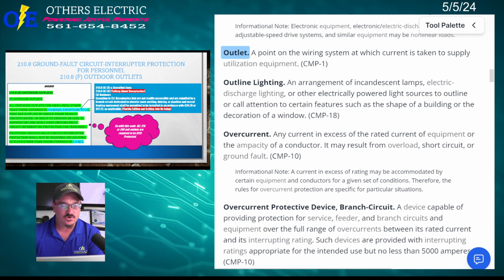Okay, all outdoor outlets for dwellings other than those covered in 210.8(A)(3), exception to 3, that are supplied by single-phase branch circuits rated 150 volts to ground or less, 50 amps or less, shall have ground fault circuit interrupter protection for personnel. So anything 50 amps or less, 120, 240 doesn't matter, because if you got a 240 volt outlet for a condensing unit, it doesn't matter. When you go either phase to ground, it's 150 volts or less. It's 120 volts. So they got rid of that 120, 240 volt thing. It's 150 volts to ground.